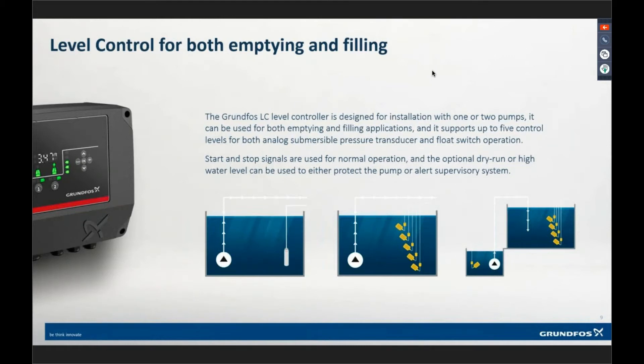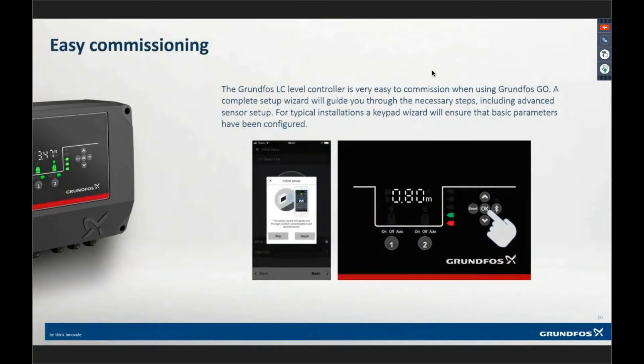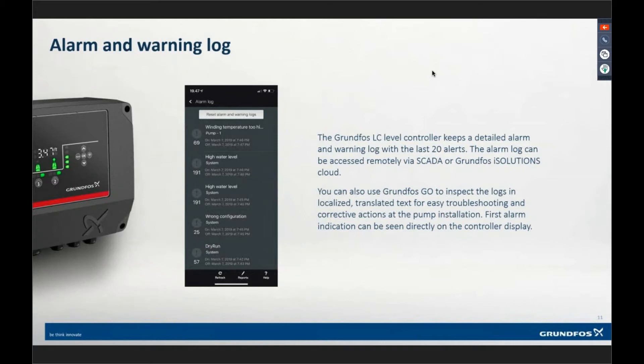Depending on your combination of floats and whatever you're doing to run the system, you can run it in either empty or filling mode. When setting up the control system, you can set it up from the keypad — which will walk you through voltage, full-load amps, and basic questions about your station — or you can use the app on the left-hand side, which has a setup wizard. Inside the control, one of the functionalities is storing the last 20 alarms and warnings. You can extract that data through the Grundfos GO app when you connect.